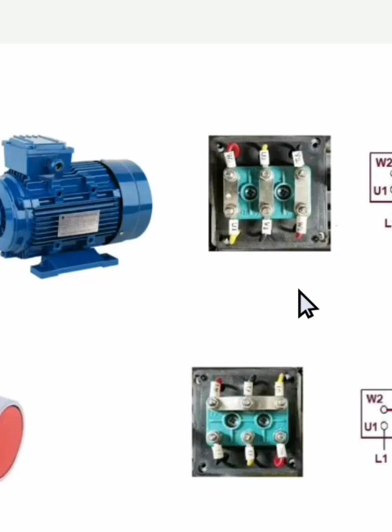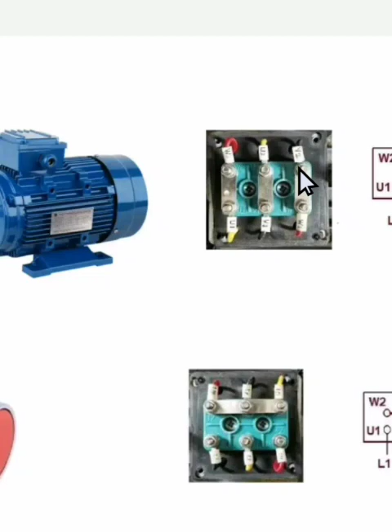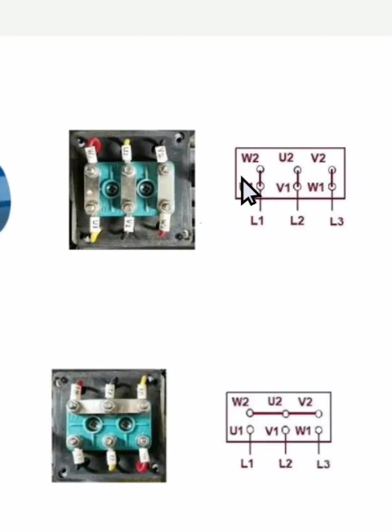This is a delta connection, where the motor is connected in delta, shown here. You can connect the three-phase cable across any of these leads, either below here or up here. This is for delta connection, as you can see. So L1, L2 can come below, or at W2, U2, V2.